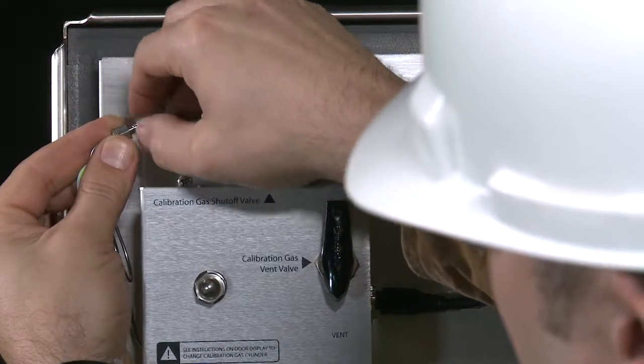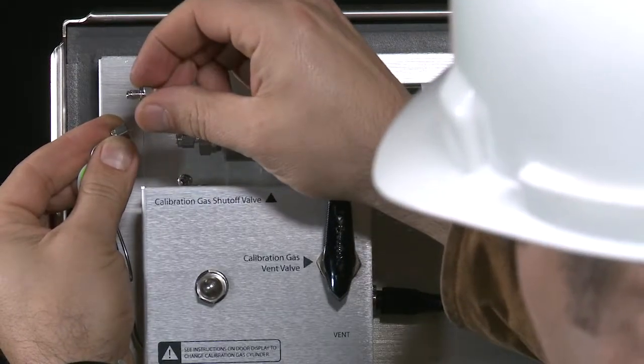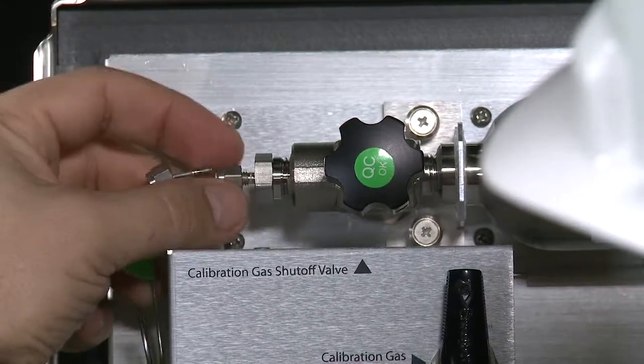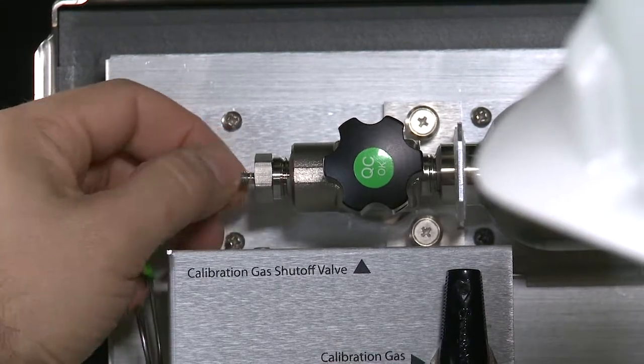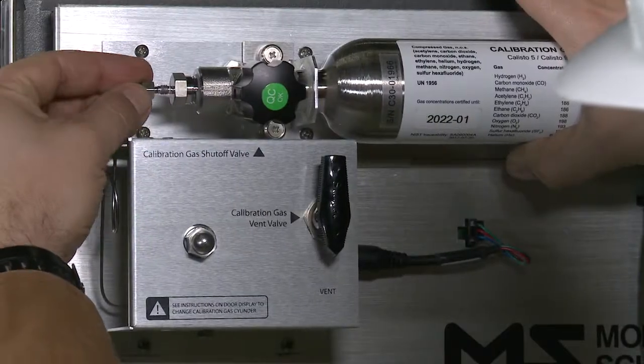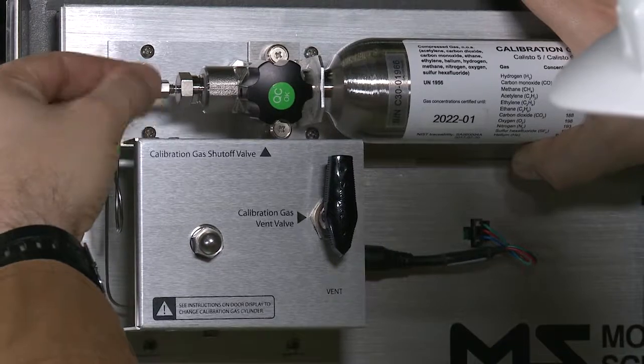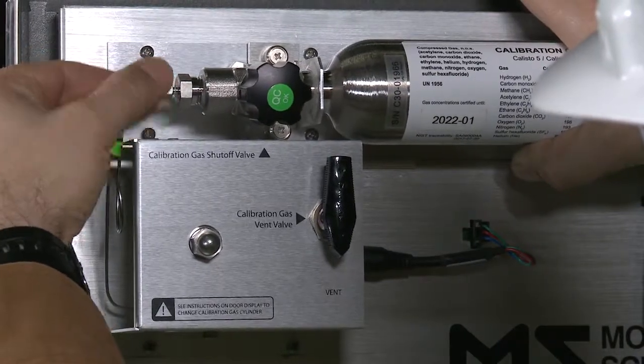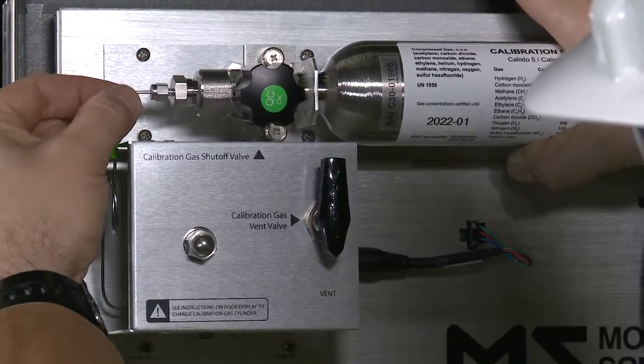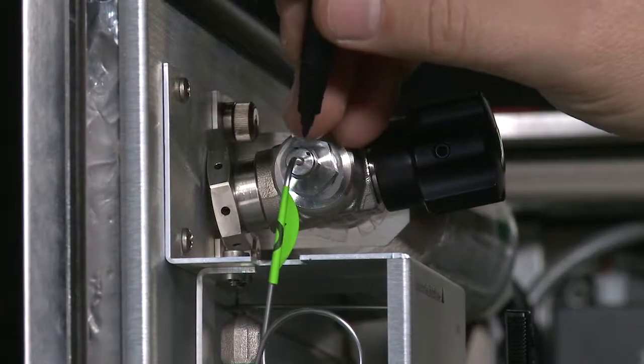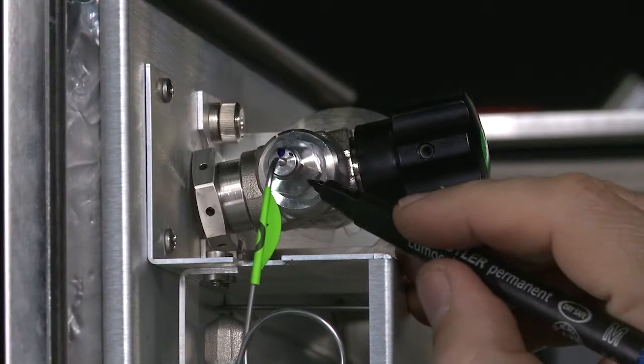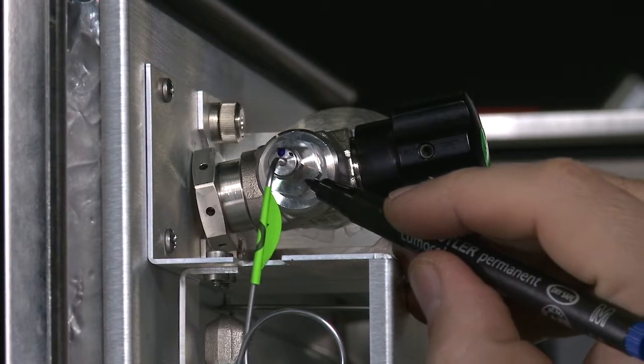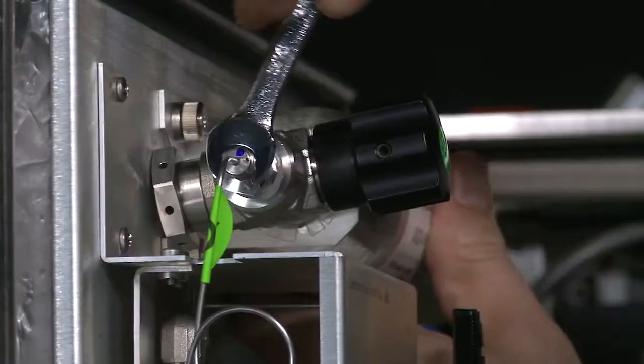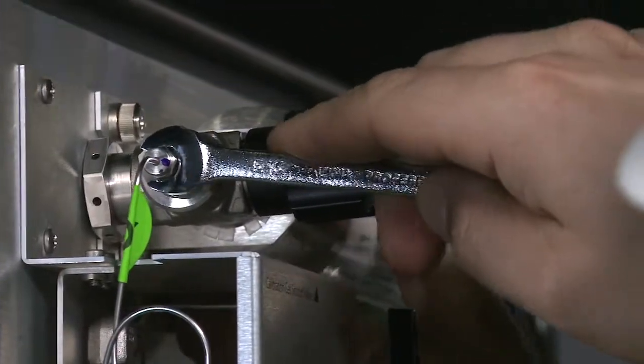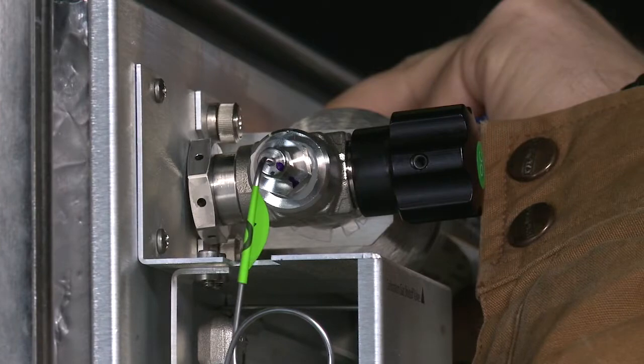Remove the plug from the tube and the cap from the cylinder. Finger tighten the tube nut to the calibration gas cylinder fitting. Use a 5/16" open-end wrench and a 9/16" counter wrench to tighten the cylinder fitting by 3/8 of a turn.